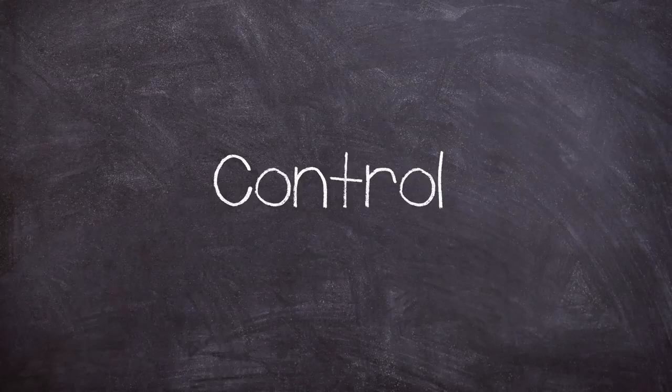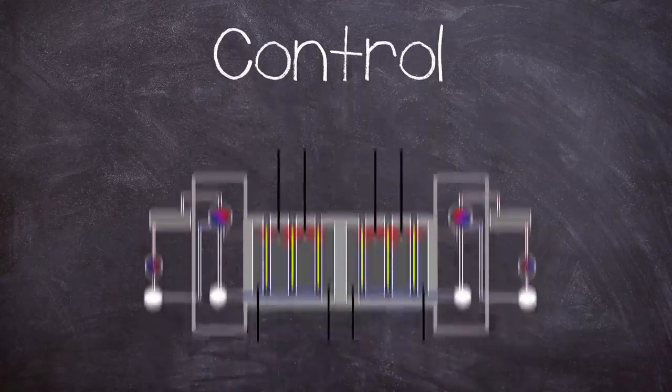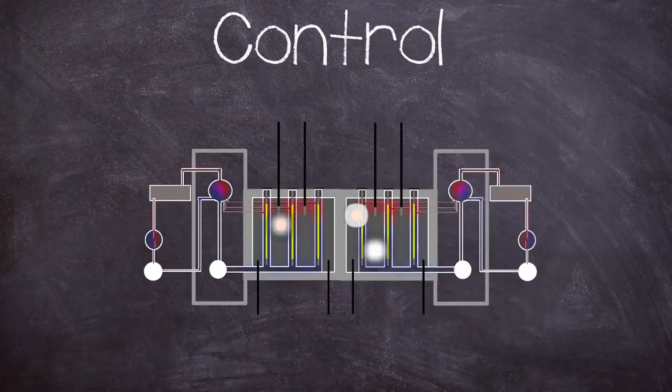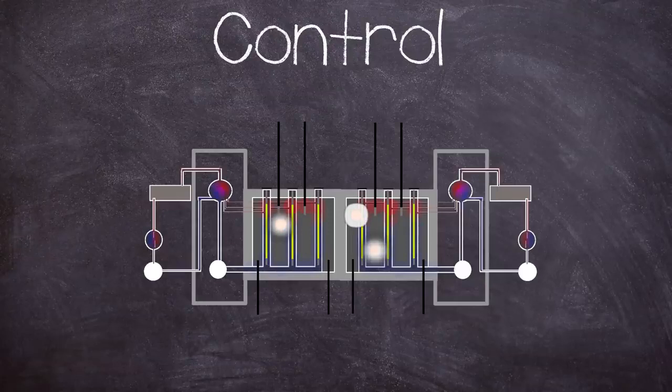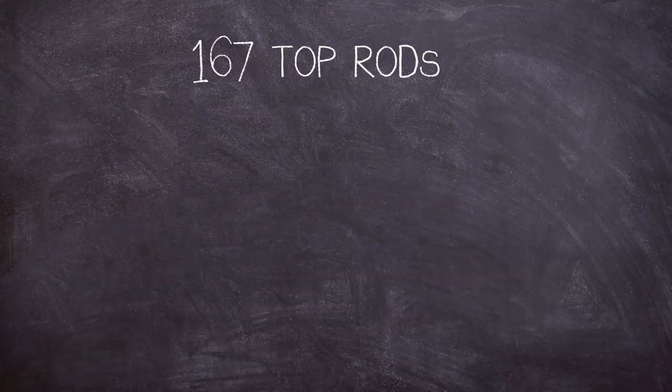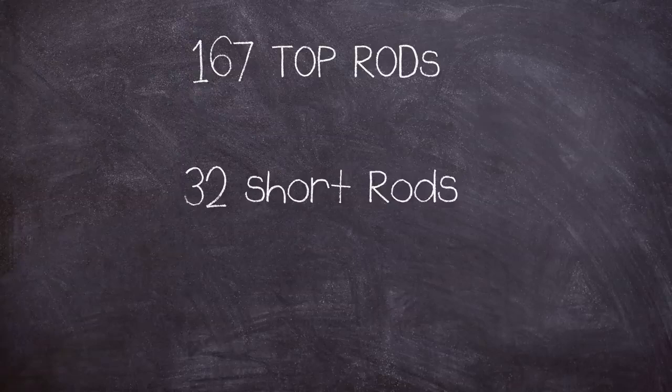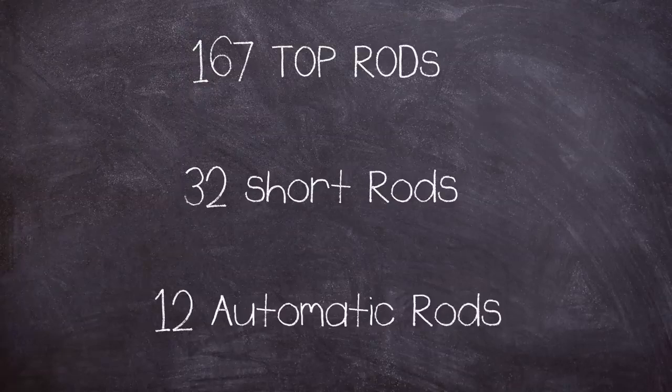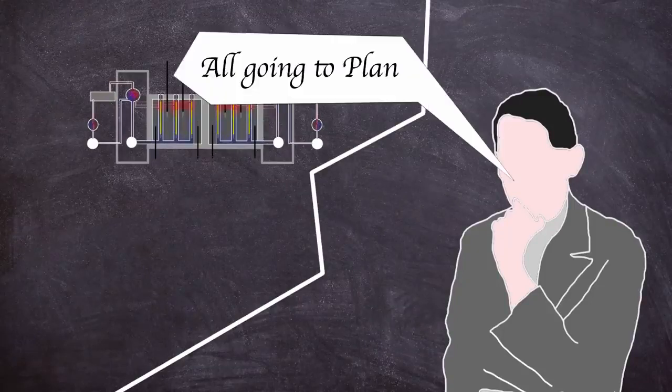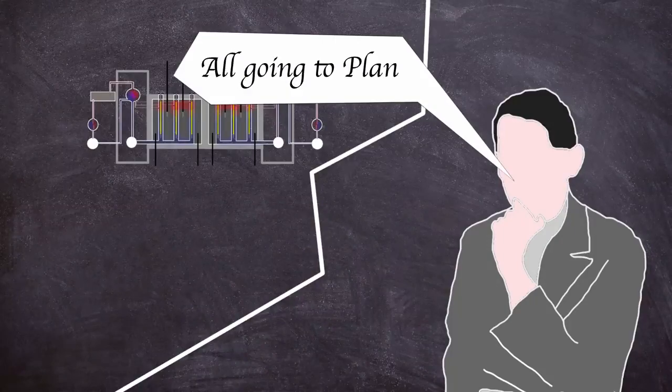This leads us to reactor control. The core region was rather big, meaning the RBMK was like multiple smaller reactors in that hotspots could occur which needed to be individually managed. This leads to the strange design choice for both top loaded and bottom loaded control rods. There were 167 top loaded rods and 32 shortened rods loaded via the bottom, and another 12 automatic controls inserted from the top. The shortened rods were used to manage axial power distribution necessary due to core size to manage hotspots.